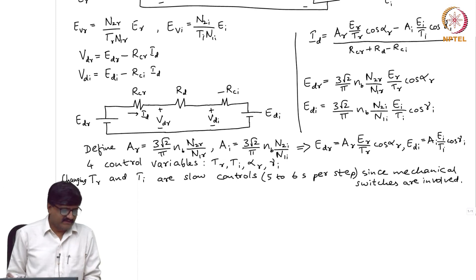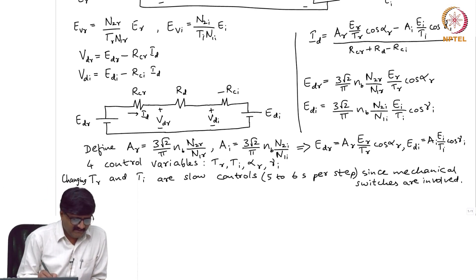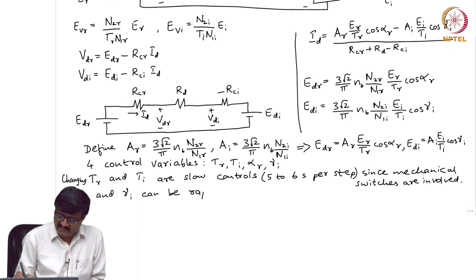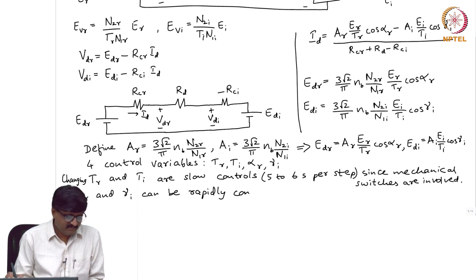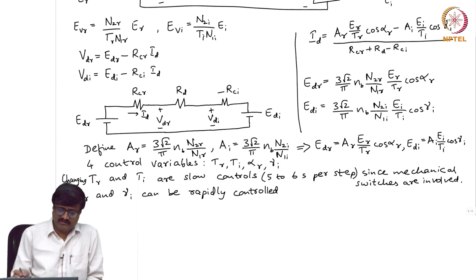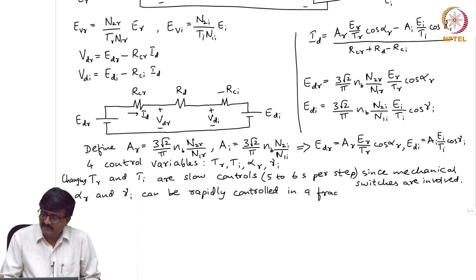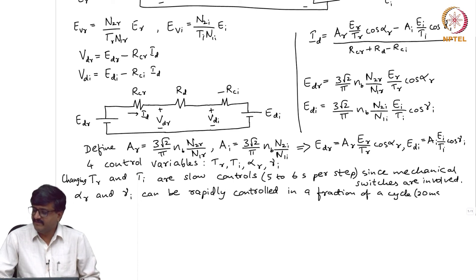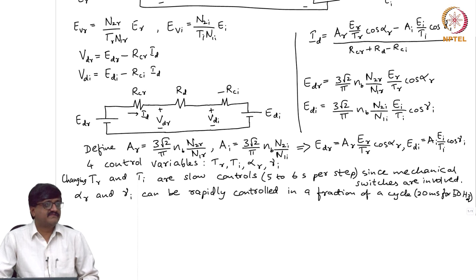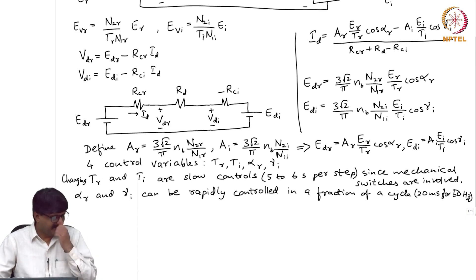Alpha_R and gamma_I can be rapidly controlled. When we talk about controlling alpha_R or gamma_I, the time required is not in seconds but a fraction of a cycle. For a 50 Hz system, one cycle is 20 milliseconds, so changes are on the order of tens of milliseconds — much smaller and hence much faster than the mechanical tap controls.